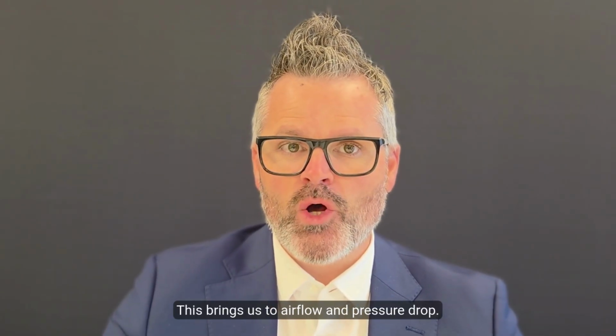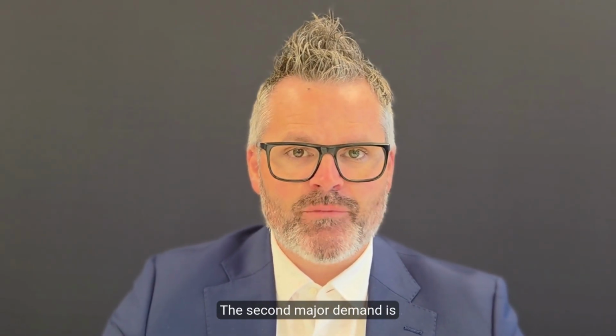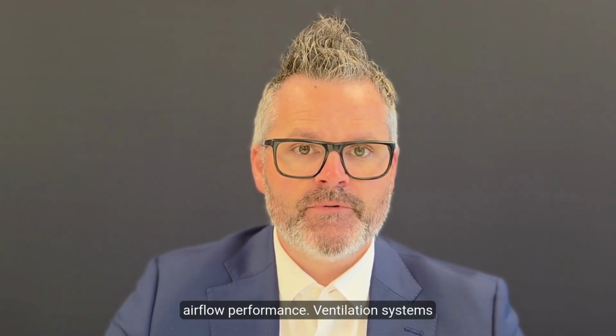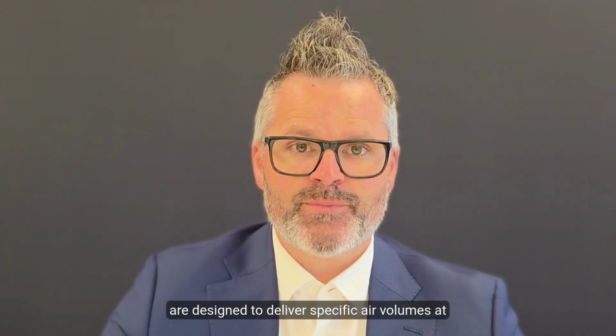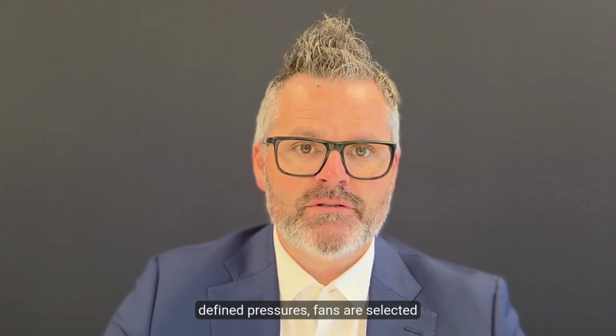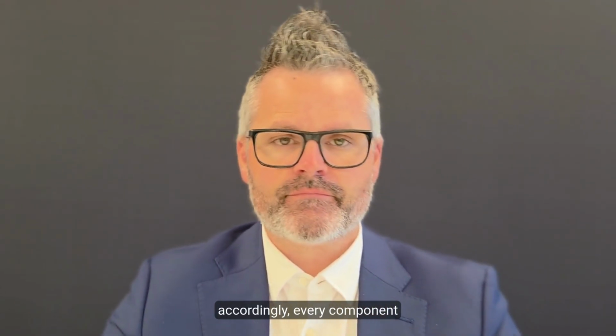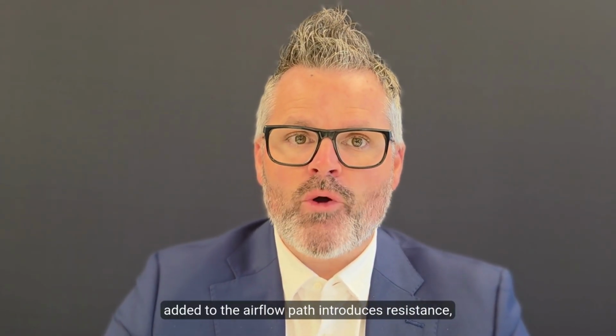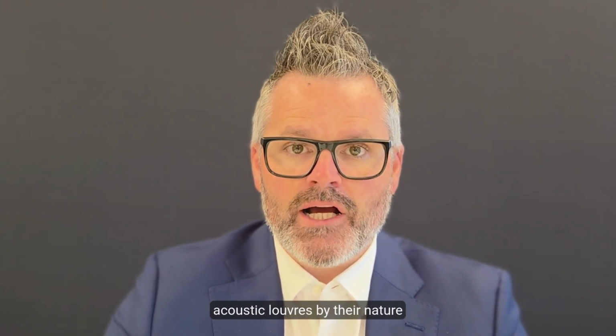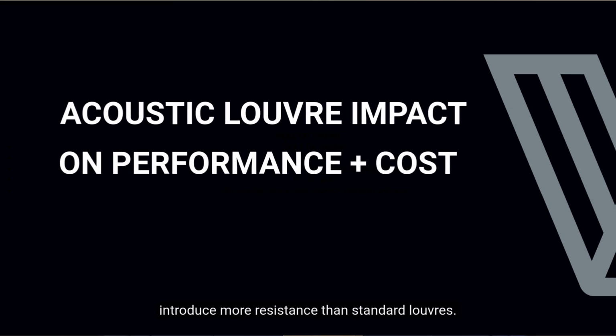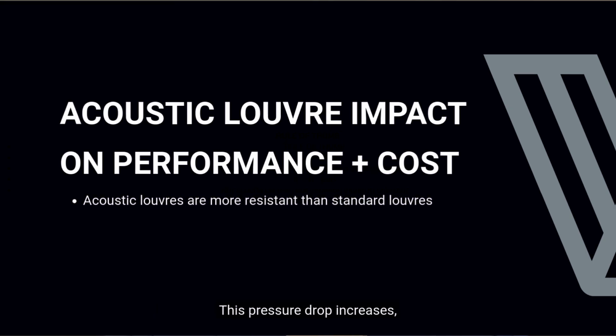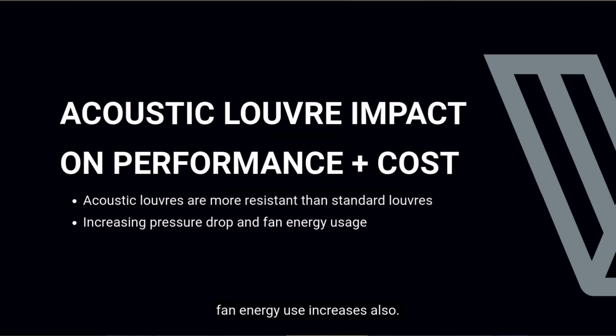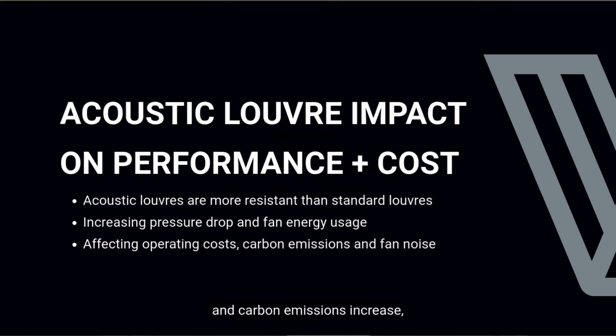This brings us to airflow and pressure drop. The second major demand is airflow performance. Ventilation systems are designed to deliver specific air volumes at defined pressures. Fans are selected accordingly. Every component added to the airflow path introduces resistance. Acoustic louvers, by their nature, introduce more resistance than standard louvers. As pressure drop increases, fan energy use increases also. Operating costs rise and carbon emissions increase. And in some cases, fan-generated noise also increases.